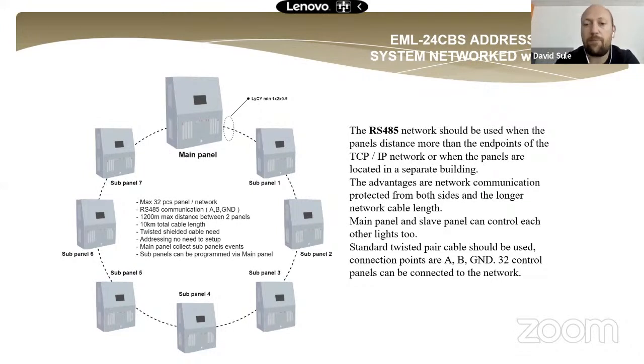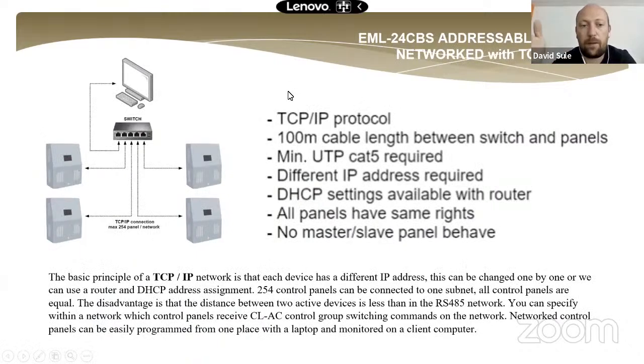For example, we have two separate buildings, and in one building we can use TCP/IP networking. But the TCP/IP networking rule is a maximum 100 meter length cable can be connected from the active devices.